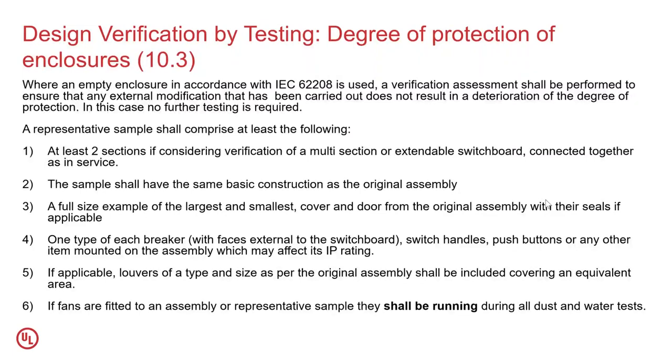If fans are fitted in the assembly, our representative sample should also be in running condition. Don't forget this. If it's a forced cooling panel, whenever you're doing IP testing, you have to switch on the fan and do the IP testing. It's a very, very important point to remember.